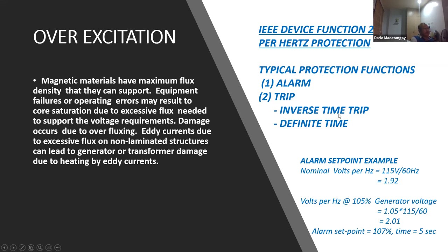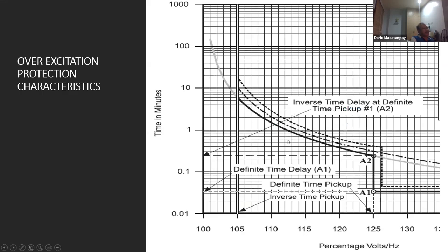So that's how you set it. This is a typical excitation protection characteristic. You have this pickup here. This is your inverse time here. So you can see this is time in minutes, and this is the percent volts per hertz. As you increase the volts per hertz, you are actually decreasing the amount of time to trip. Here you can see this is definite time pickup at this point. So at 125%, the time needed to trip it is about 0.05, okay?